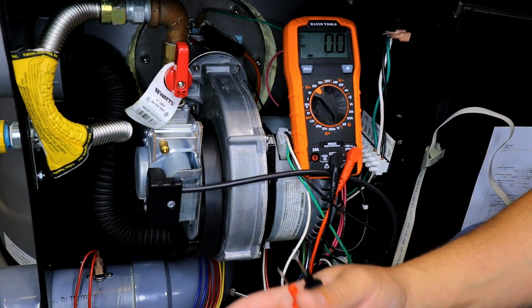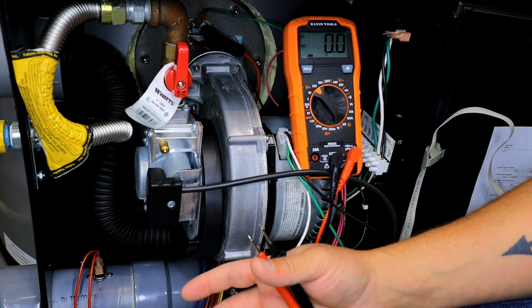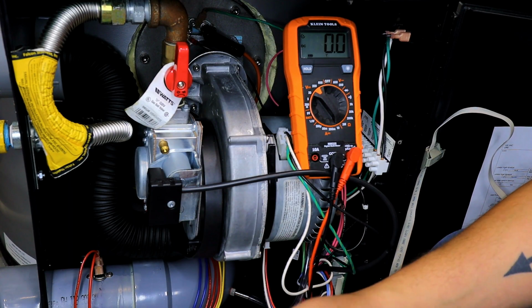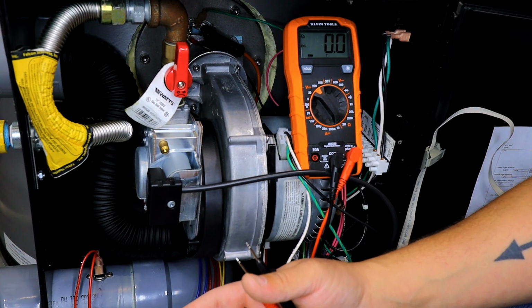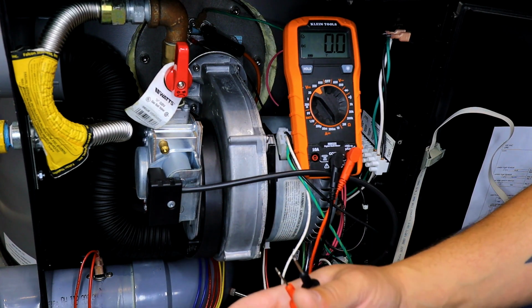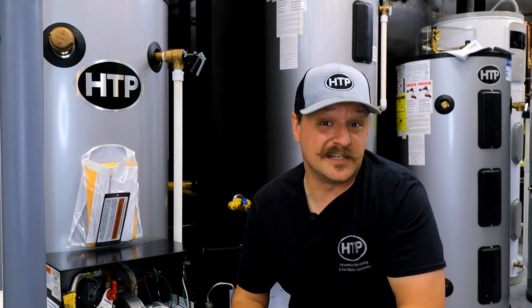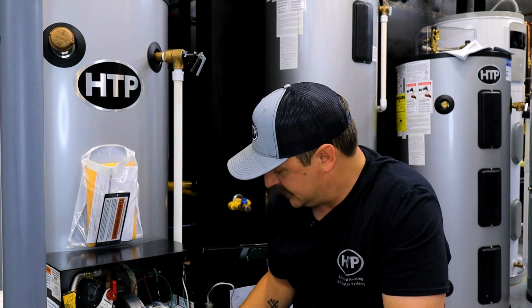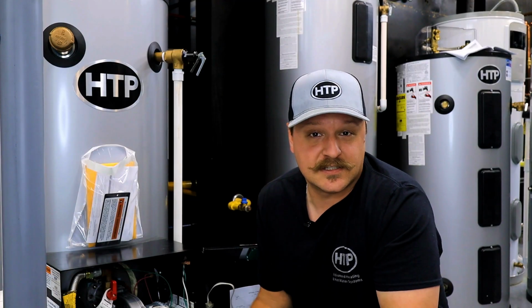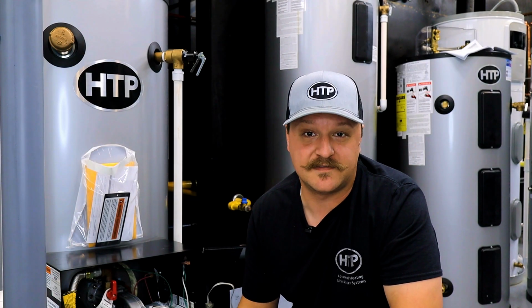So essentially, when we're testing our low voltage, we want to see somewhere between 34 and 36. That is usual normal operation, but we can be anywhere between 24 and 42 volts. So now that we know what optimal running conditions look like, we know how to diagnose the unit. So if the fan is energized and we disengage this low voltage input and the fan doesn't move at all, it's a good chance you've got a seized fan.